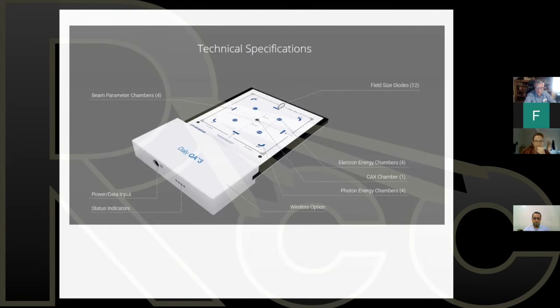But it also, very importantly, gives the therapist a number that correlates with symmetry, beam symmetry. Is the beam symmetrical, this side to this side, from here to here? So flatness and symmetry can also be monitored with this device. So this device is useful for three things: for field size, for output in the center, and for flatness and symmetry.